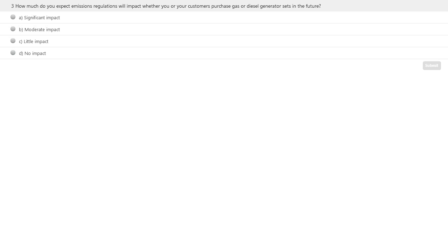So we're always looking out in front to see if there's emissions regulation changes. I believe that the biggest thing that has made the largest impact recently is going to Tier 4 in your non-emergency applications. That has driven a lot of manufacturers to create that Tier 4 final product. The other thing that was talked about earlier is that we are certainly seeing a trend towards natural gas due to the additional cost and extra work needed to get to Tier 4 final. We're seeing more natural gas applications coming because of those regulation changes.